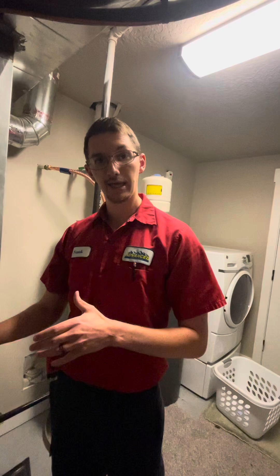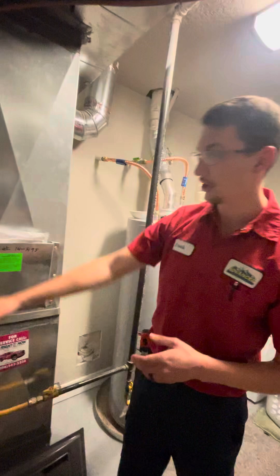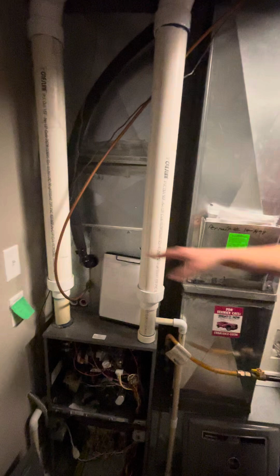To also increase a little bit of airflow, I do want to go ahead and just put it under a base can so it can actually be elevated, and we're pulling from the base can as well as from this guy, just increasing airflow and making sure those heat exchangers as well as that coil isn't going to freeze up or get too hot for them, so it'll last them a long time. We also have 2-inch going into 3-inch on the existing exhaust and fresh air on this guy. We should be able to basically just cut from either this joint and build in a coupler and just build it back down, which will be great, but this thing will be completely elevated.